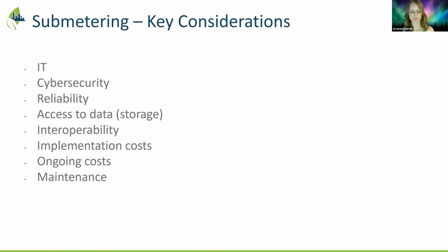And then what we're building up to is creating a standardized scope, standardized designs, brands. It depends what type of data you need, but we're looking at standardizing how long we store the data and what frequencies, 15 minutes versus hourly, tying back to one central platform. We did try several different types of meters and found they all had pros and cons. It was good to test and it was insightful, but now to manage the number of login credentials we need to maintain, we're looking to move to one centralized platform.